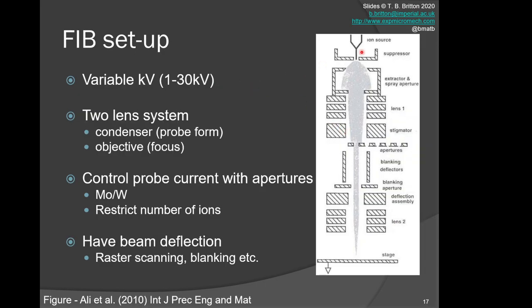We recall that in our ion beam system, we have formed our ion source with our wetted tungsten needle. We have formed this to extract off that, and we can control the probe current by balancing the extractor and suppressor. Over time, the gallium can oxidize, and there's some balancing. This is why the FIB tip may need to be changed occasionally—it's effectively because the source no longer wets effectively. We can then control the probe current by changing the spray aperture in the system and the final aperture.